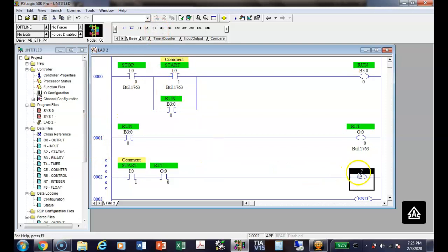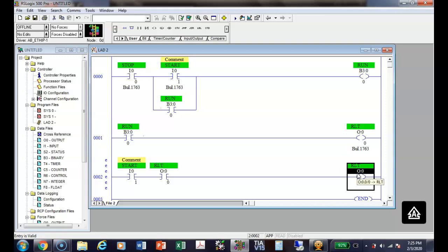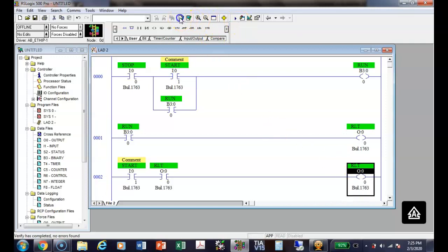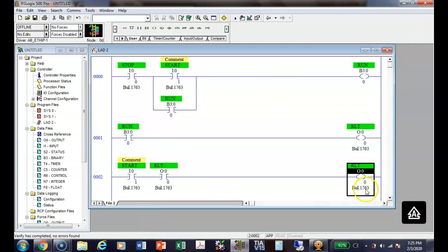With PLCs, we can use that address as many times as we want to. Here, we'll assign this to another output. By the way, you don't want to do this. RLT. Notice, I'm going to come up here and check this right here. It's going to say I have no errors because it's in the right syntax. What I've done is I've assigned two different rungs that has different logic. I've assigned it to the same output.